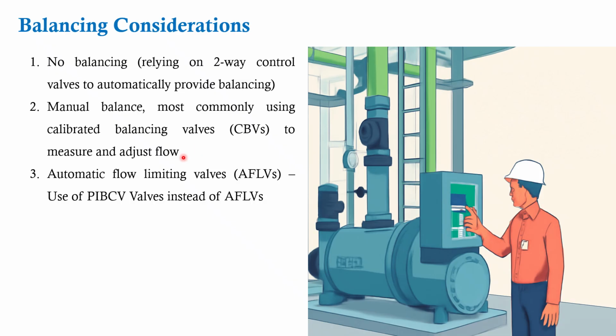The third is an earlier case wherein people were using the automatic flow limiting valve. The limiting valve was having the pressure drop. Actually, it was pressure dependent valve. It is not a pressure independent valve. So it is better to use the pressure independent balancing control valve instead of AFLV, the automatic flow limiting valve. The reverse return, I think I discussed in my previous video also. Here I am going to touch upon how reverse return also helps in balancing the water flow in the HVAC plant room and the system.